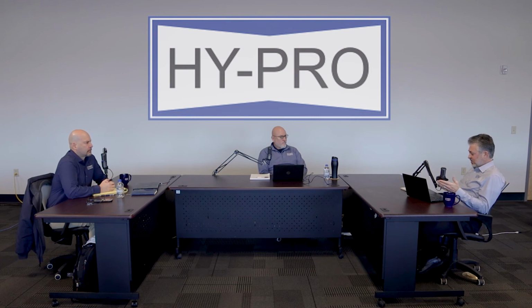You're definitely taking that conversation away from that 10 micron statement and starting to pry and ask questions, because ultimately, like you both said, we have an ISO code limit that the system should operate under. And we call it a limit, not a target, because a target is something to achieve and a limit is something to avoid. We have to determine what that limit is, based on the most limiting component, and then determine what efficiency media is required. Just looking at media grades doesn't tell the full picture. The operating conditions of the system are a factor as well, like ingression rate. So just a 10 micron filter is an invitation, if you ask me, to start a conversation.